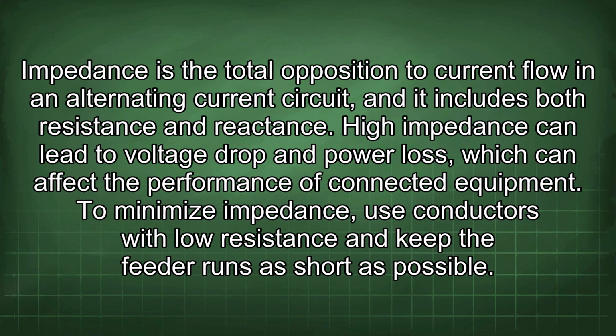Impedance is the total opposition to current flow in an alternating current circuit, and it includes both resistance and reactance. High impedance can lead to voltage drop and power loss, which can affect the performance of connected equipment. To minimize impedance, use conductors with low resistance and keep the feeder runs as short as possible.